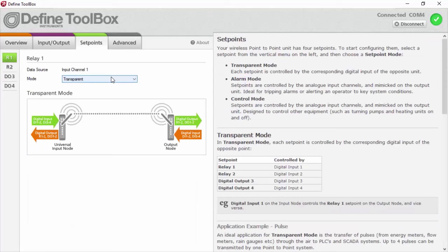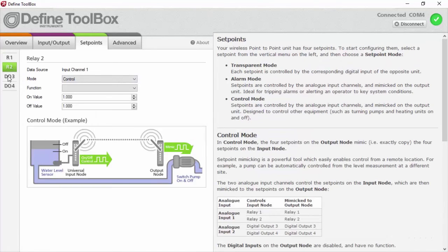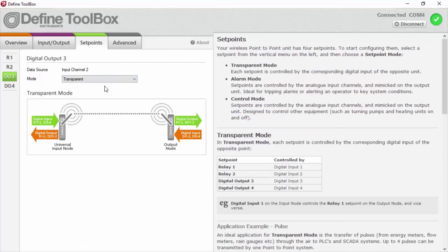The set points are what we're going to use to control the pump. On the output side, we have 2 relays and 2 digital outputs. At the moment, you'll see that each of these is in transparent mode. Sorry, that one's still in control. But the rest of them by default come in transparent mode. So what the transparent mode does is there's inputs on the input side, and the state of them is sent to the output side, and when they're in transparent mode, they will echo exactly the logical state that you see on the input side. So if you close the contact here, you'll close the contact there.